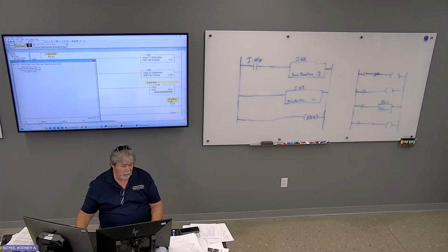Junk about the processor nobody really cares about. Scan times. Overflow trap, which is right there. If you do a boo-boo in your math and you try to divide by a 0, or put a number in a register that doesn't fit 16 bits, you can go up to 65,535. Anything more than that doesn't fit because there's only 16 bits. You'll get a math overflow. If you don't do this overflow trap unlatch, the very last thing in your program, and something like that happens, it'll fault your controller. If you put that in there, it won't.